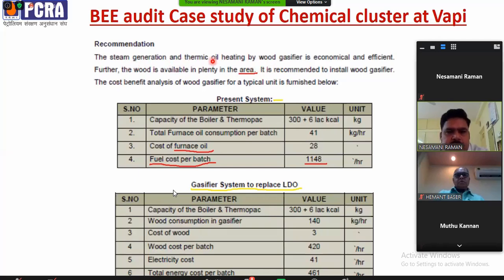The steam generation and thermic oil heating by wood gasifier is economical and efficient. Further, the wood is available in plenty in the area. This needs to be taken seriously, because only if your location has access to good quality wood can you switch over. Otherwise it will be a problem, because the transportation cost will add further. So it is recommended to install a wood gasifier.